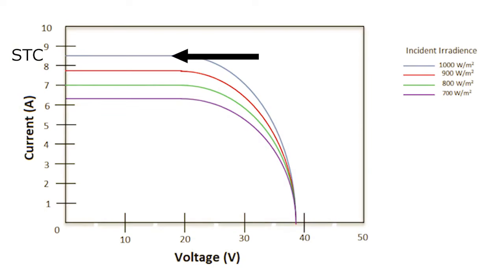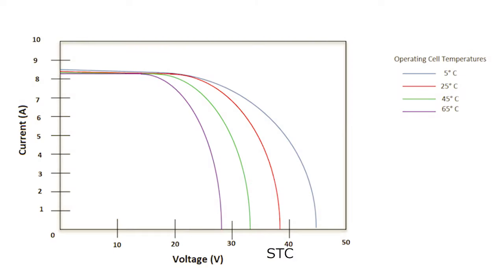As you see here, the current will go down as the brightness of the sunlight goes down. So, if you have a cloudy day, a photovoltaic module will still work, it will just output less than its maximum power because the current has gone down. There's also a temperature dependency value because solar panel voltage decreases as the cell gets warmer. So, the efficiency goes down slightly from standard test conditions. Now, this isn't a big deal for efficiency, but it can be really important as we begin to choose proper wiring. We'll discuss that in the next course.